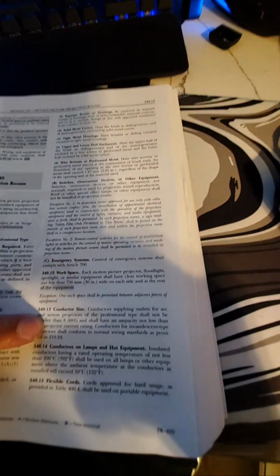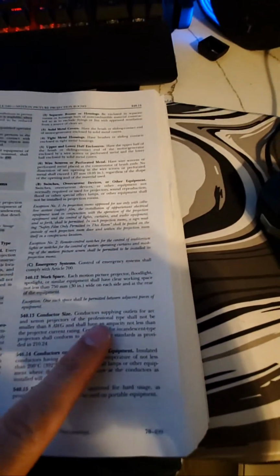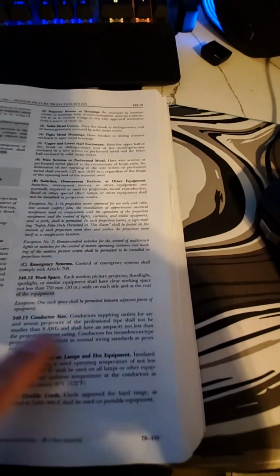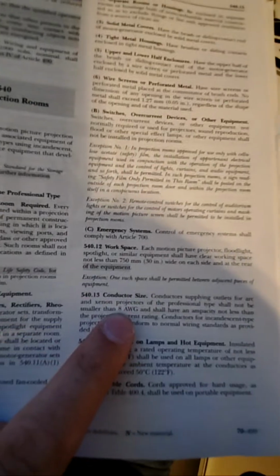Types. Switches. Conductor size. Here it is here. It's actually 8. Check it out. Conductors supplying outlets for arc and xenon projectors of the professional type shall not be less than number 8. There it is there.